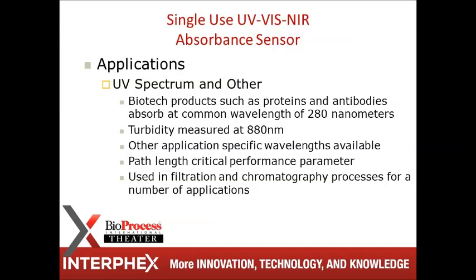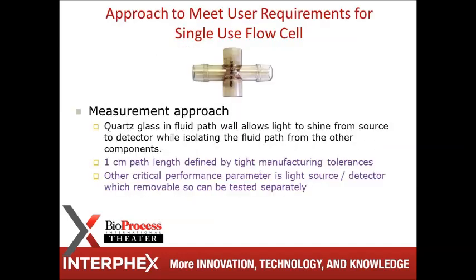In terms of UV absorbance, that's a different type of measure. The actual sensors aren't touching the fluid. It's shining through the light path. And I think a lot of people are familiar with UV or turbidity. The important aspect of this is the path length. What's the path length that you're measuring? And it's very applicable to filtration and chromatography processes. But in this case, the sensor basically just gives you a window to the fluid, and the monitor is really the key performing factor in your measurement.